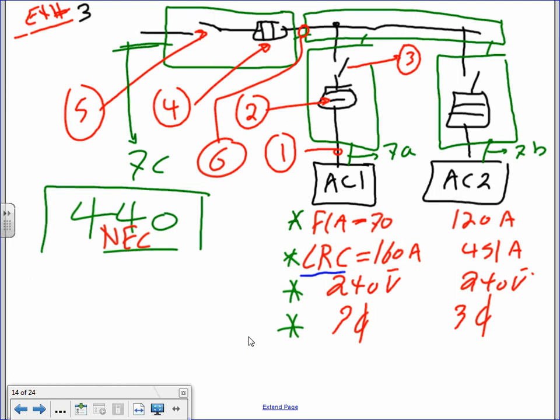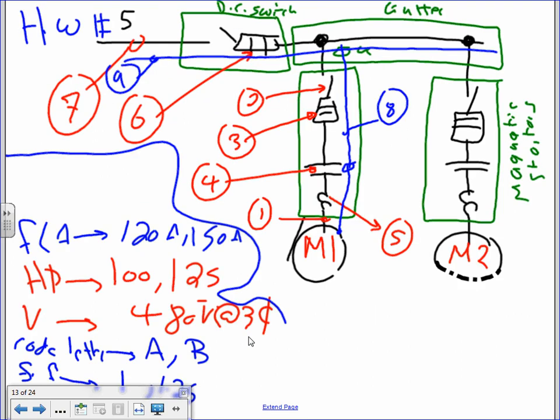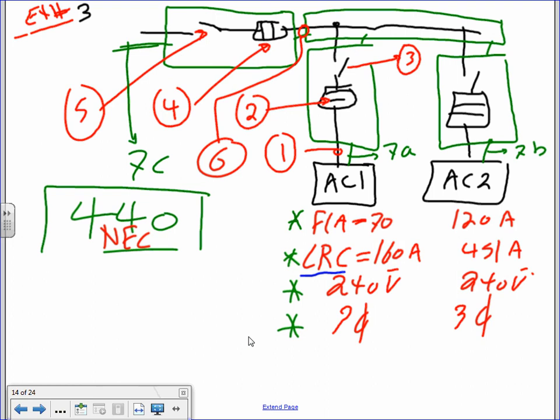For HVAC equipment — typically chillers — we typically have a fuse disconnect with them. What happened to the controller? For chillers and rooftop units, the controller and the overload tend to be part of the manufacturer-provided controller. The manufacturer has a little VFD or controller attached to the equipment, and all we have to provide is a disconnect. There's no separate controller — just a fuse disconnect.